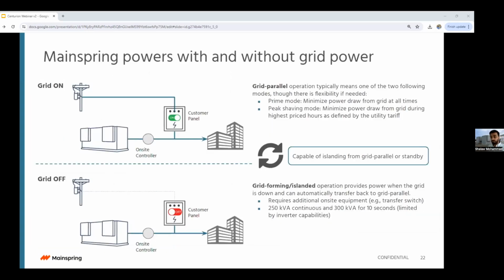All right, so modes of operation, we do have 2 modes of operation. We can run in grid parallel mode, which means that we are syncing into utility frequency and voltage, and we're just offsetting utility kW. And typically this is done by us installing a meter at the incoming utility and monitoring what the incoming kW is and trying to drive that to the difference.